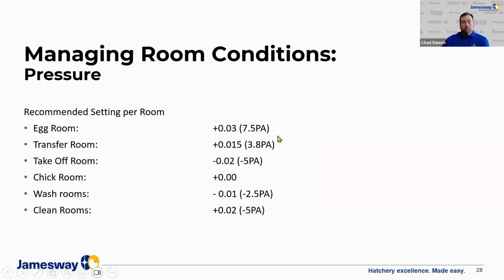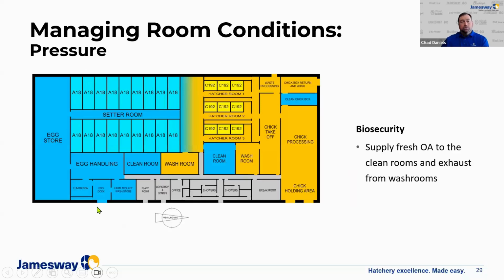These are some additional recommended pressure settings for rooms outside of the incubation areas, such as the egg room. The transfer room should be somewhere between what our setter room and our hatcher rooms are. The takeoff room, where we pull the chicks, is the most negative room in the hatchery. And then we have chick rooms, washrooms, and clean rooms. When we look at washrooms and clean rooms, oftentimes in this dirty end of our hatchery, we have a room where we store our clean chick boxes. And that's in the dirty end of the hatchery. The way we have to try to manage that is that the dirty chick boxes are coming into this washroom.